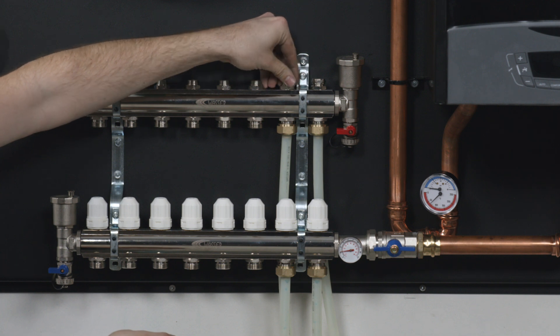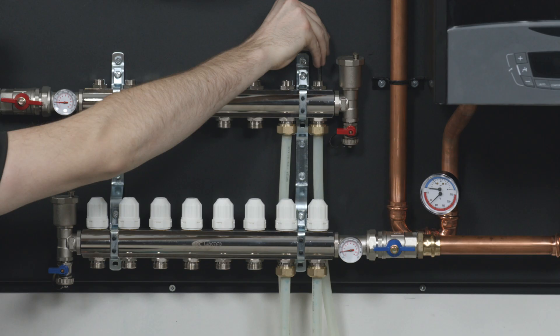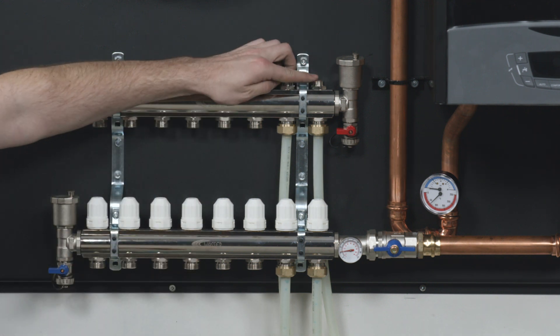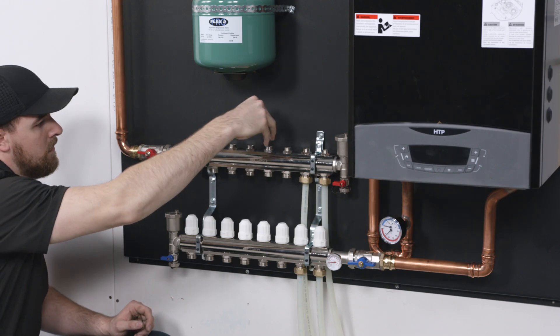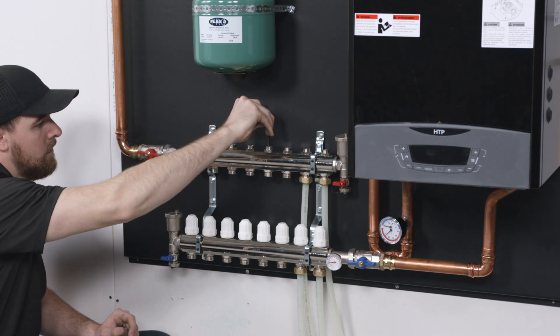Open the manifold valves with an Allen key under the hex cap on the manifold. It will be fully open when it is flush with the top of the threaded seat. With the Allen key, close any unused manifold ports and cap the open ports.